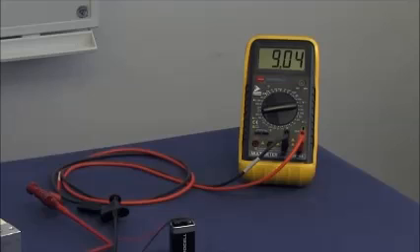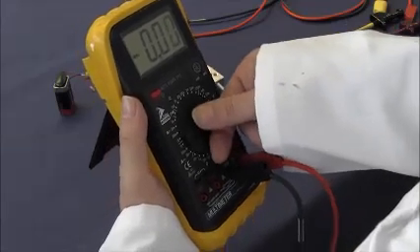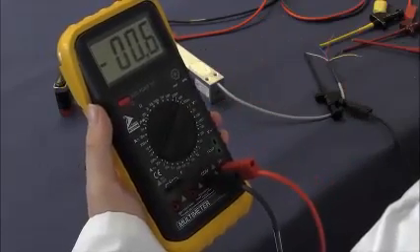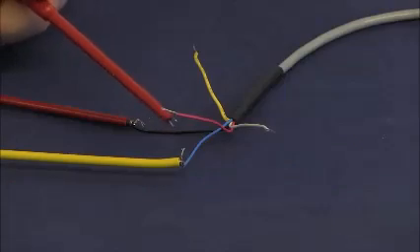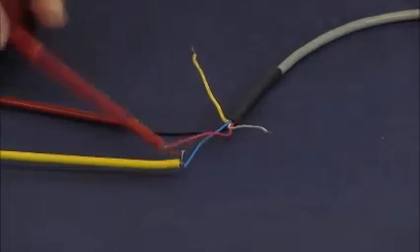Wait for approximately 5 minutes for the load cell to thermally stabilize. The measured value with no load applied should vary only by a few digits around zero. With the multimeter, the smallest measuring range is 200 millivolts.